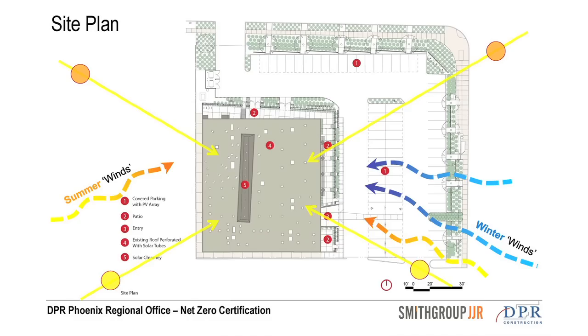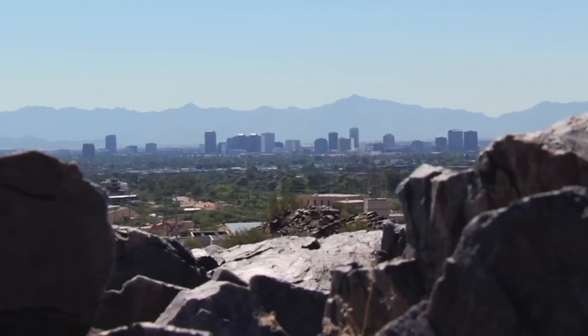My main vision for the project was to deliver a design that would allow us to maximize the natural ventilation. We did some early analysis that showed natural ventilation in the Phoenix region would probably be effective for around 24% of the operating hours of the building. That's not a great percentage, and hard to justify the cost for natural ventilation at that lower percentage. So my goal was to strive to design a system that would allow that percentage to increase. Our goal was something around 36% of the time using natural ventilation.